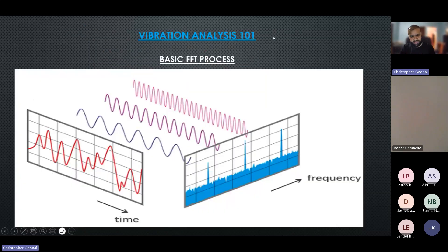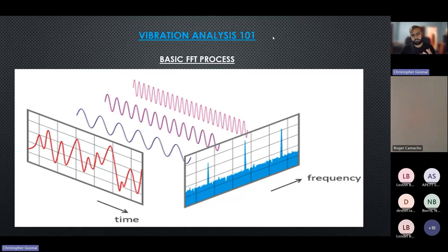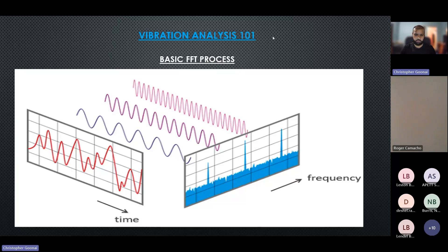Now the vibration analysis 101 — the FFT process. It starts with a complex waveform, and what the FFT algorithm does is extract from that waveform its individual sinusoidal or frequency components. Each waveform may have a separate frequency, and you map those out on a spectrum — a measure of amplitude versus frequency. You can see in the illustration in blue how all the individual frequencies are mapped out, and you use those patterns for vibration analysis to assess the machines.